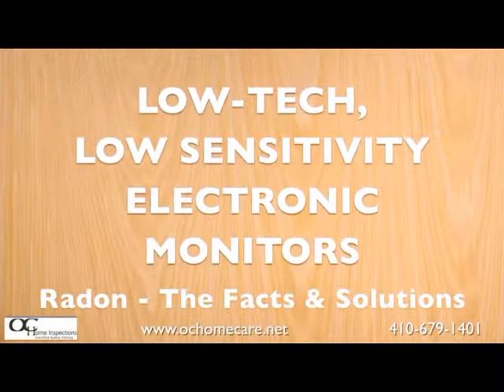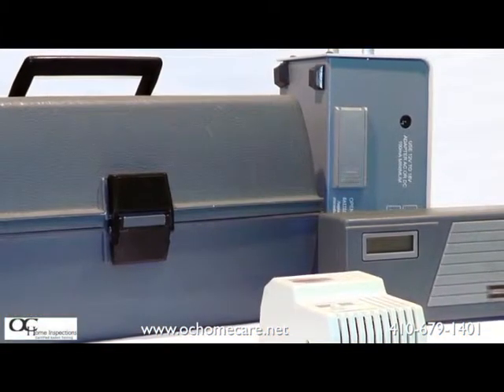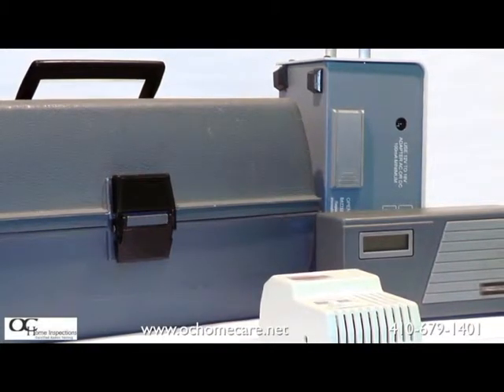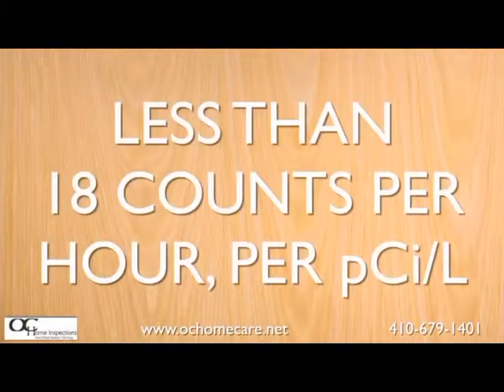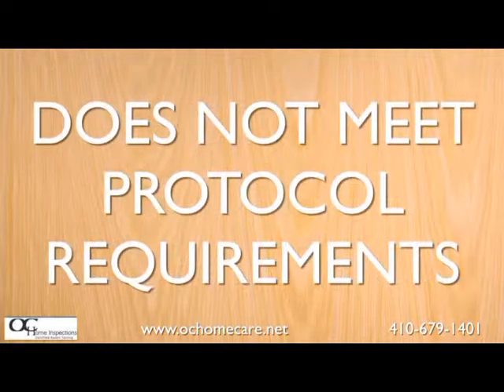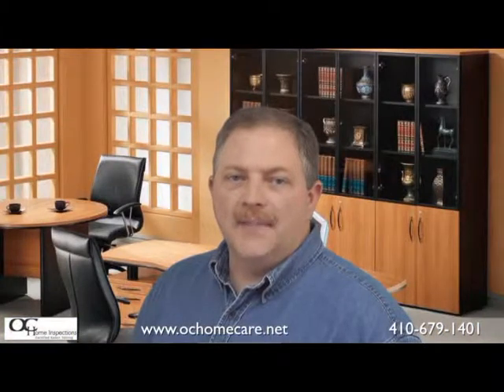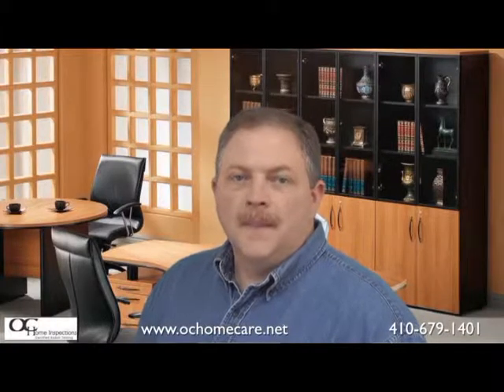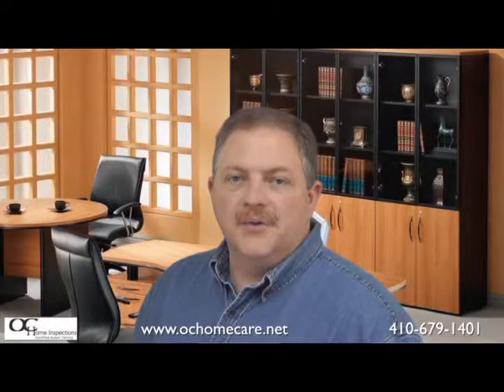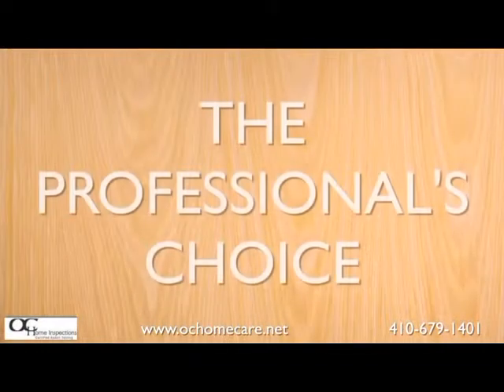Next is the low-tech, low-sensitivity electronic monitors, which are purchased and used by many home inspectors simply because they're cheap, and it allows them to operate under the radar screen of the National Proficiency Program and some of the state licensing programs. While these devices are often referred to as continuous monitors, their low sensitivity of less than 18 counts per hour per picocurie per liter of air means that they do not meet the single device testing options for real estate testing, and two devices must be placed side-by-side for a valid and proper test. They may be a little bit better than passive devices, but there can only be minimal assurance that these monitors are maintained and properly calibrated.